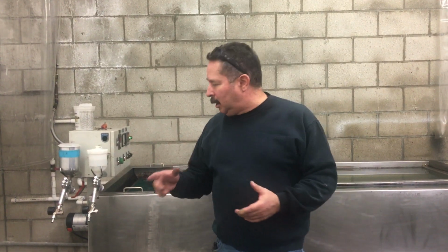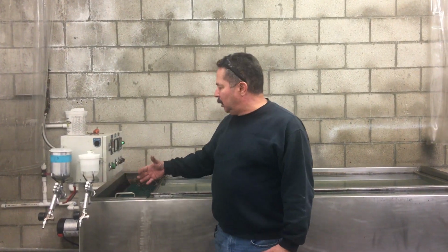So, correct size volute - yes, you do need a large volute. It moves the amount of water you actually need, not only to clear the surface of the water, but also to get the heat out of your sump side. One thing we noticed with the smaller pump was that it wasn't moving the heat from the heat exchangers out to the body of water.